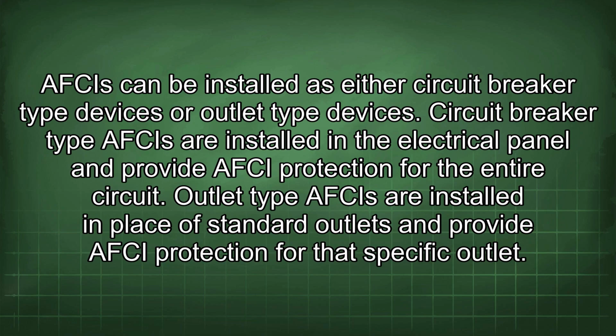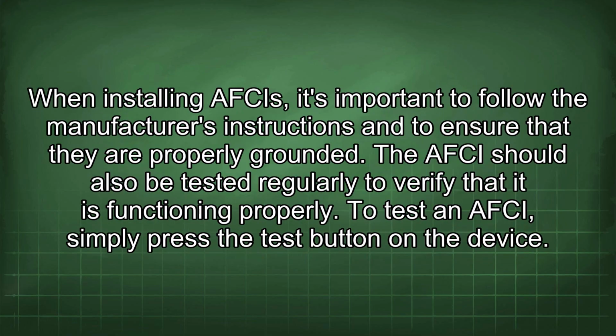AFCIs can be installed as either circuit breaker type devices or outlet type devices. Circuit breaker type AFCIs are installed in the electrical panel and provide AFCI protection for the entire circuit. Outlet type AFCIs are installed in place of standard outlets and provide AFCI protection for that specific outlet. When installing AFCIs, it's important to follow the manufacturer's instructions and to ensure that they are properly grounded. The AFCI should also be tested regularly to verify that it is functioning properly.